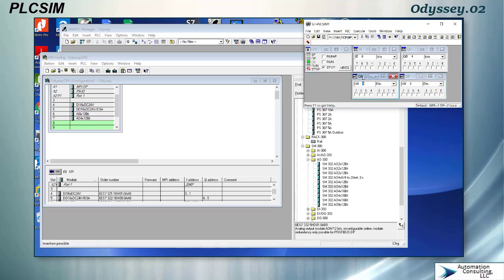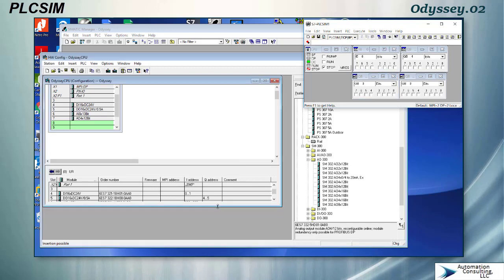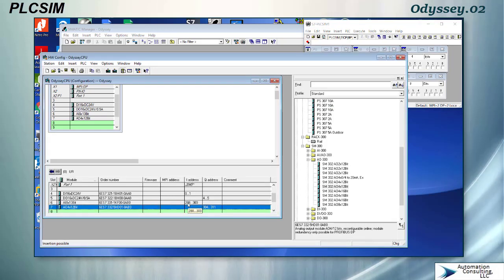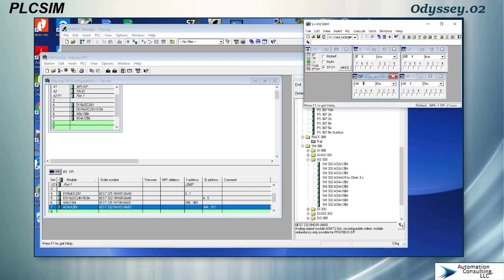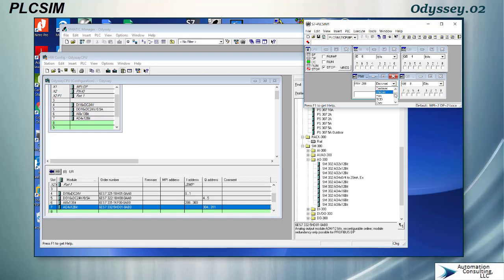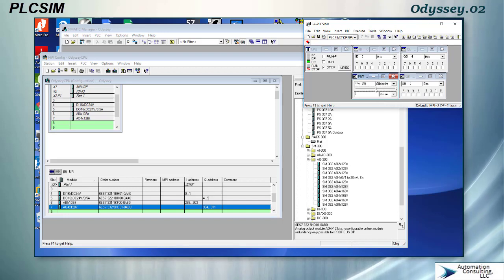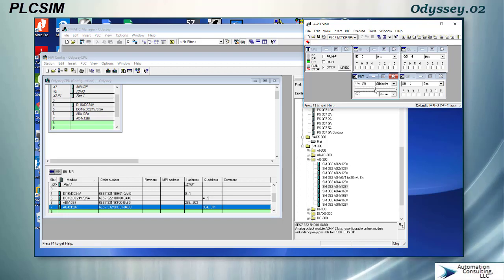For analog there's a couple different ways that you can display your analog. If I put in this address down here, PIW, so process input word 288 for the entire word, obviously I'm not going to show the bits, it just shows it as decimal. But one of the cool things about Siemens simulator is that I can also make it a slider. Two different kinds of sliders, this one goes negative and positive. We'll use this one, this would simulate something like a negative 10 volt to positive 10 volt signal.